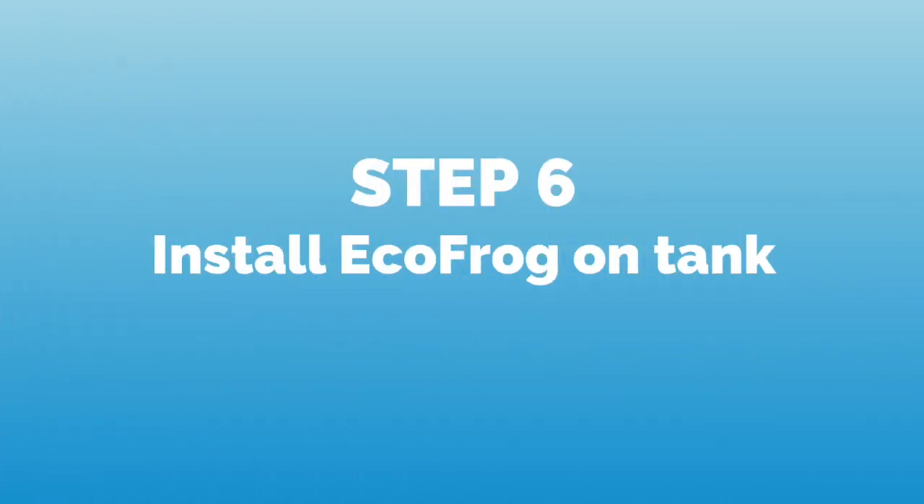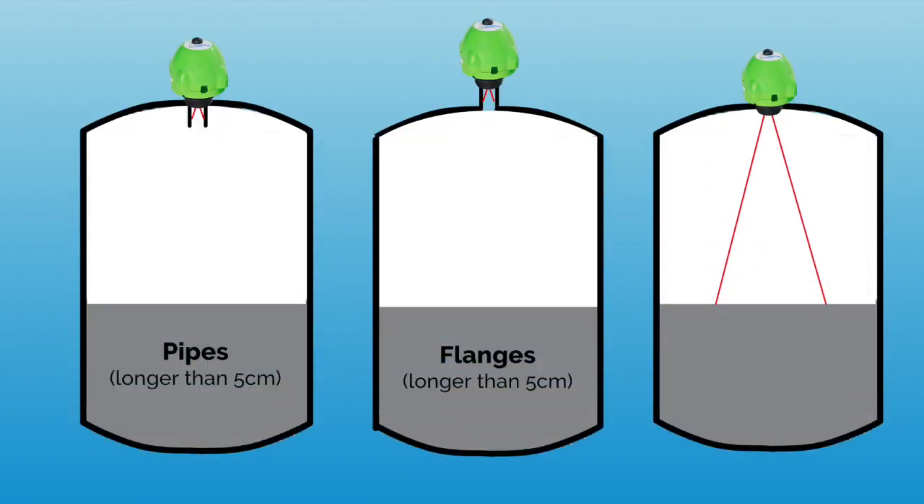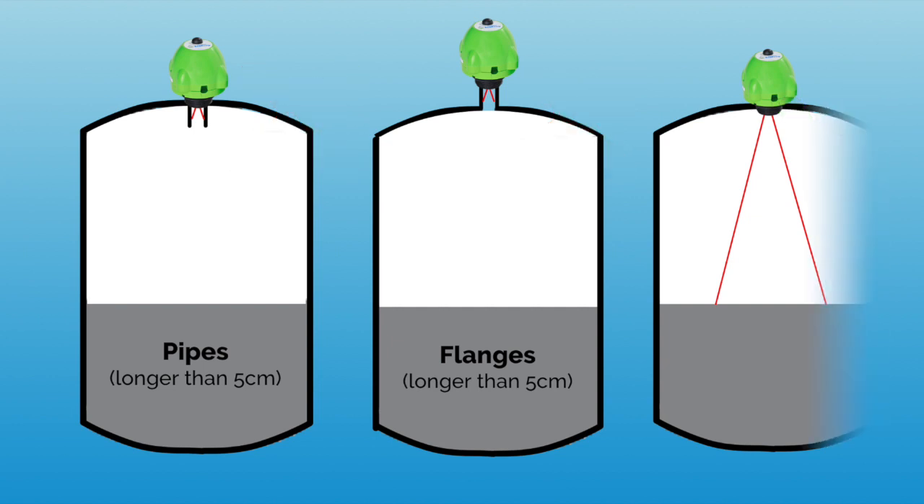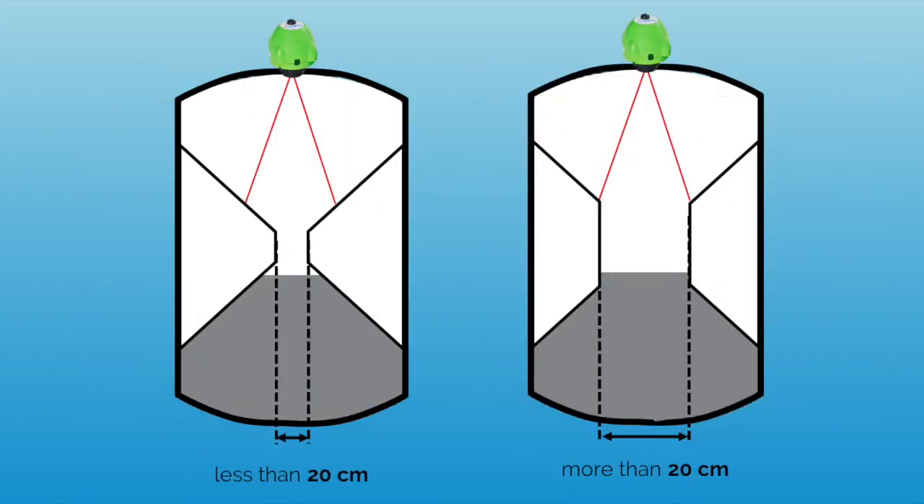In the last step, we mount the EcoFrog on our tank. Make sure that we have not installed a sensor on pipes or flanges longer than five centimeters, but that the ultrasonic waves of the sensor enter your tank unobstructedly. In addition, check that your tank does not have any side indentations that leave less than 20 centimeters diameter space vertically under the sensor.